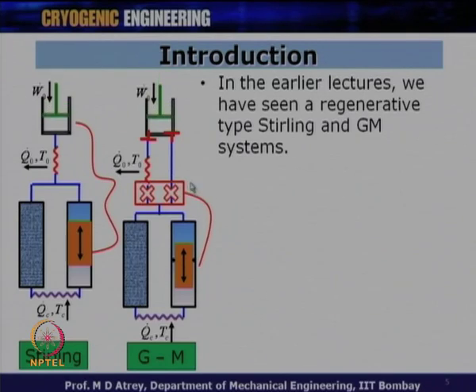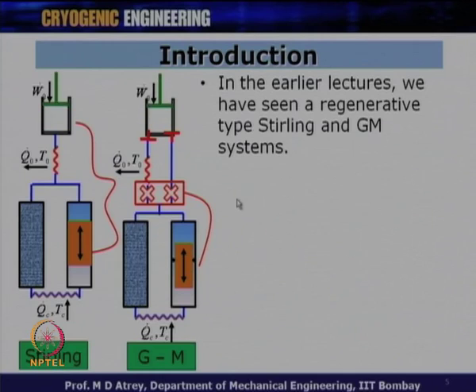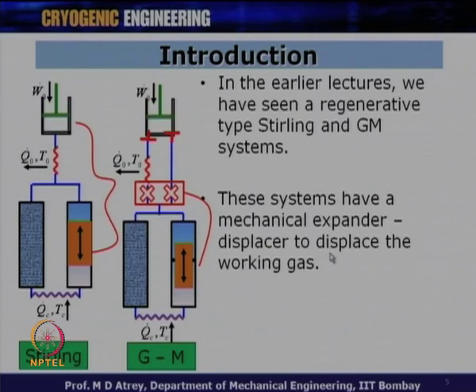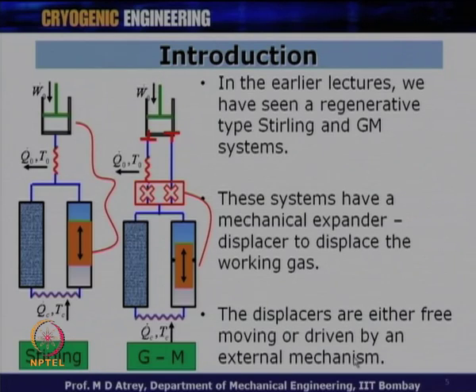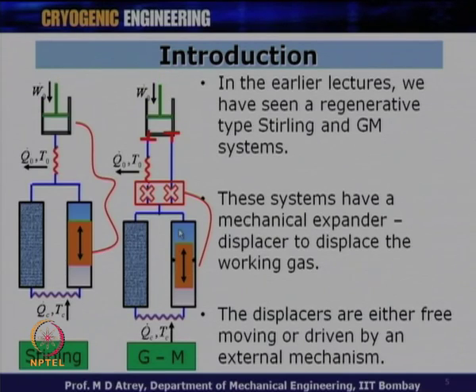In the GM cryocooler, the phase difference is between the valve mechanism and the displacer, which moves at a relatively low frequency. Both Stirling and GM systems have a mechanical expander-displacer to displace the working gas — either free-moving or driven by an external mechanism. In a free displacer, the piston moves because of the pressure drop across it. The displacer is normally a very lightweight moving component.